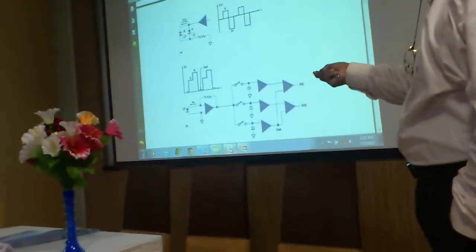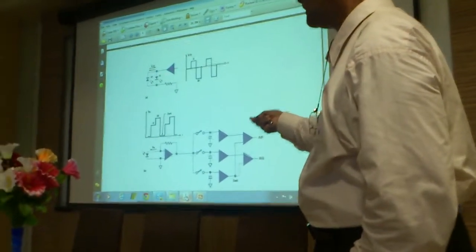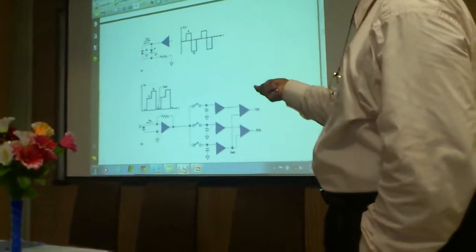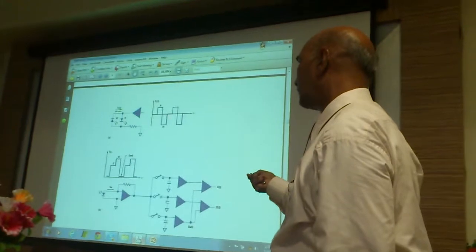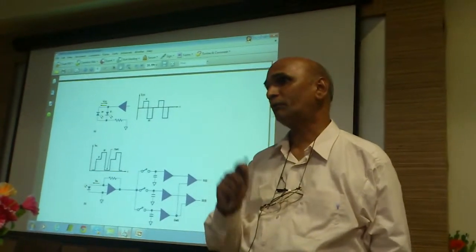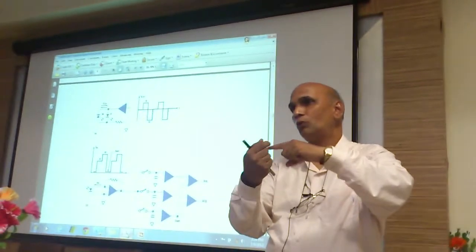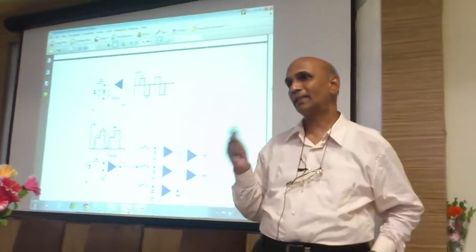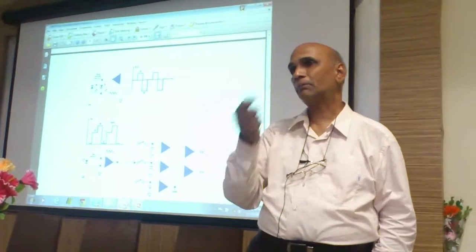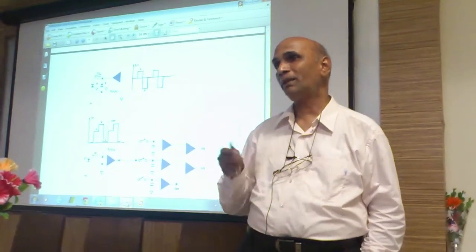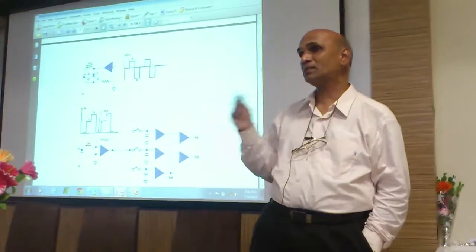The two LEDs (red and infrared) are connected anti-parallel. When the current sources out of the circuit, the red turns on; when it sinks the current, the infrared turns on. So there are three states: red on, infrared on, and both off — at which point the photodiode sees only ambient light. Ambient light is the light in the room and it is not constant — it changes with different ambient conditions. For example, during the day it is skylight; at night it is room lights. Ambient light causes a DC shift error, so the instrument must compensate for ambient light correction automatically.